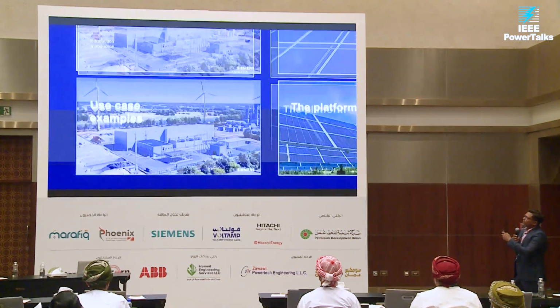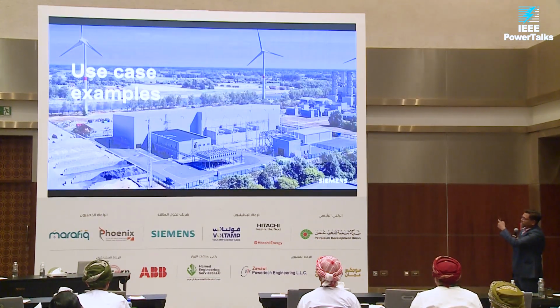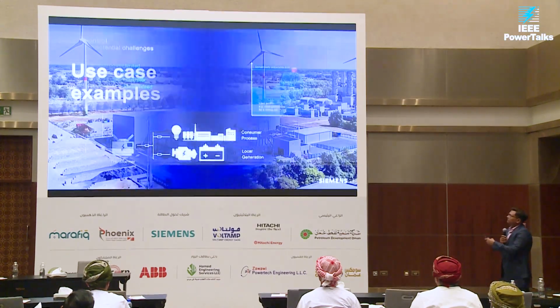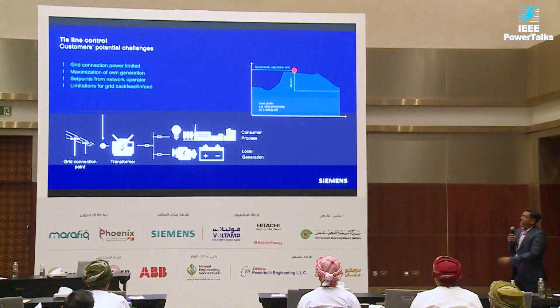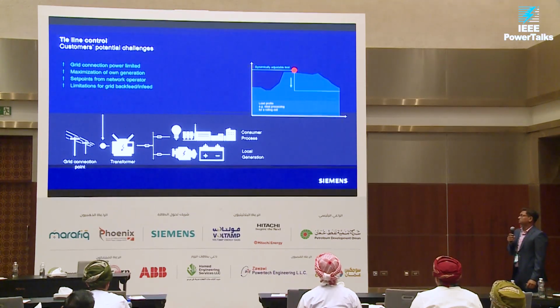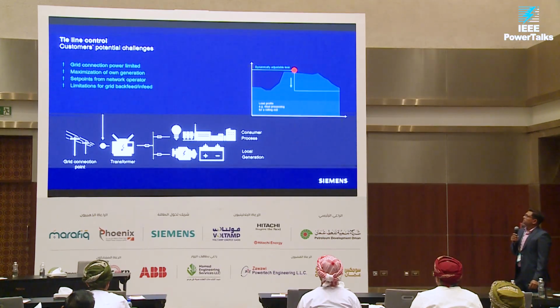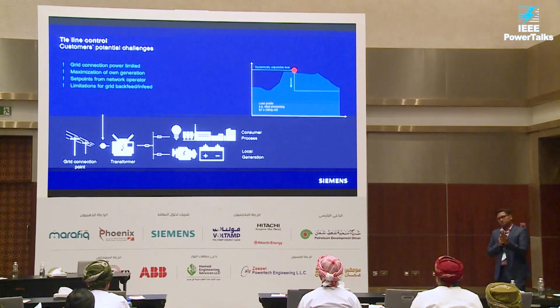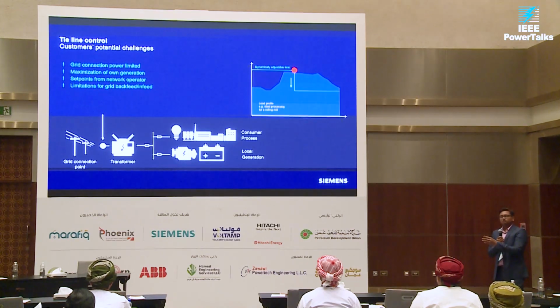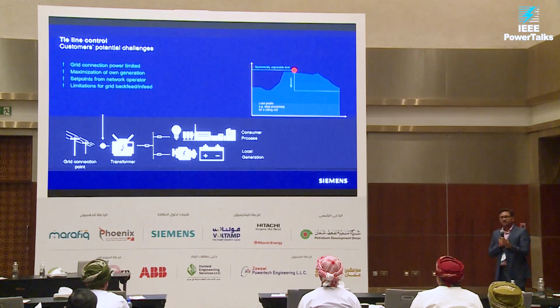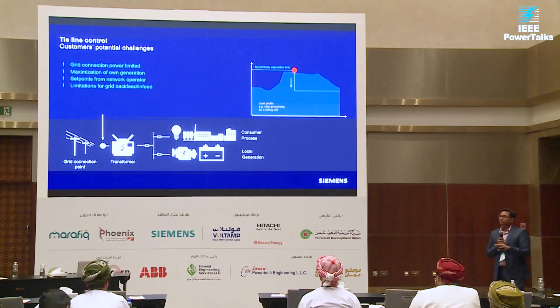So I'll take a few use case examples from the last slide, because we cannot discuss all. Basically, tie line control. It's very important, I would say it's a very important function. Tie line means, basically, if we have a microgrid, the point where it is connected to the traditional grid, that point is called the tie line, or sometimes the point of common coupling.